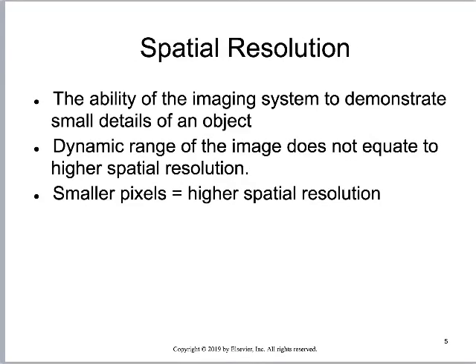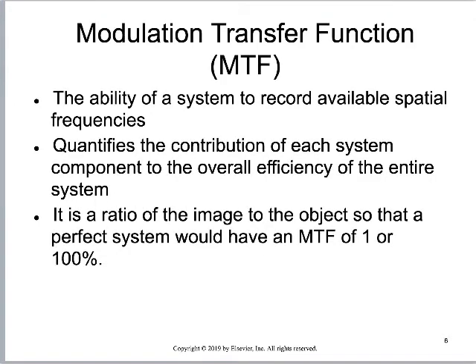Spatial resolution — the smaller the pixels, the smaller the pixel size, the higher the spatial resolution. For contrast resolution, it has to do with bit depth: how many different attenuation values can it store and recognize? Typically the way we talk about this is within the modulation transfer function, or MTF. It is a way of representing what the spatial frequency is of a given system.